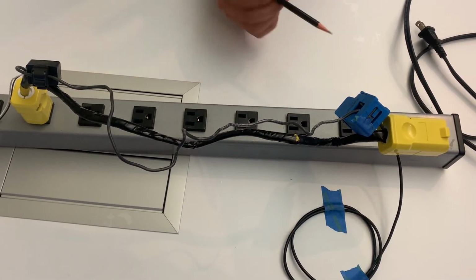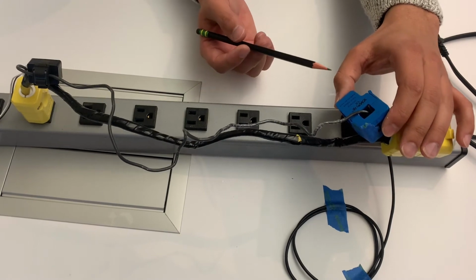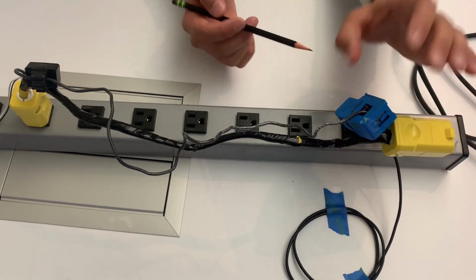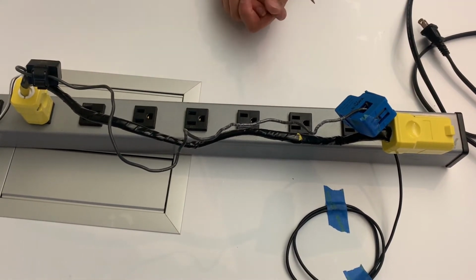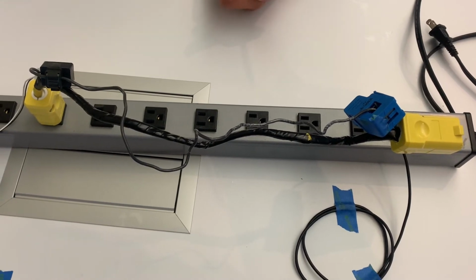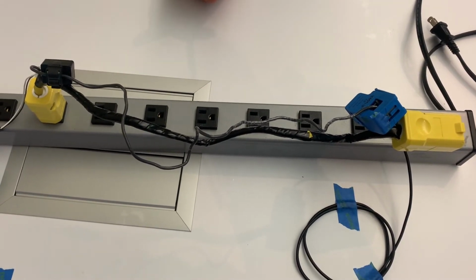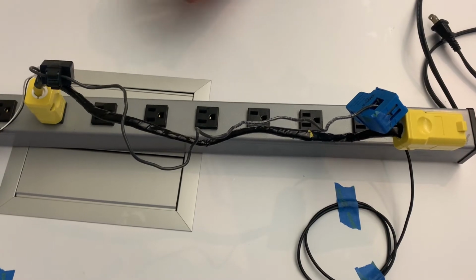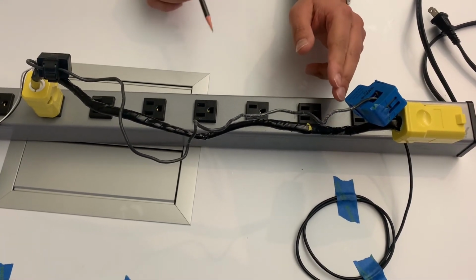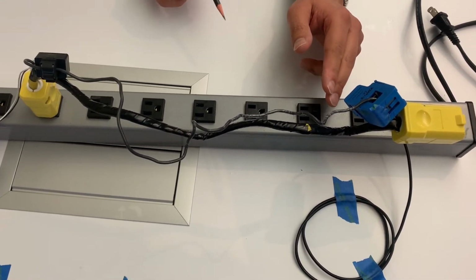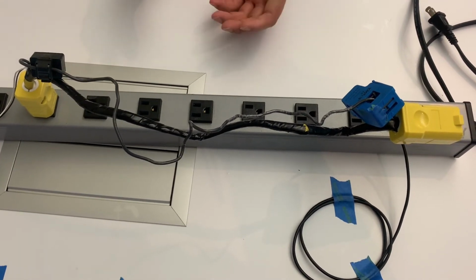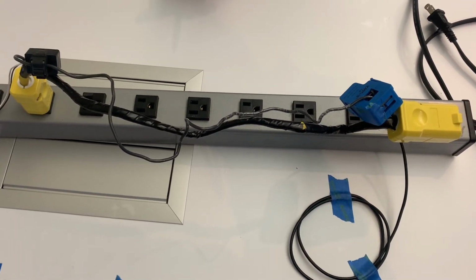Our harvesting current transformer has a 1 to 1800 turn ratio. We also have a second current transformer which we're using to take all our measurements with. It has a 1 to 3000 turns ratio. The output of the harvesting current transformer is hooked up to a full bridge rectifier and energy management circuit.